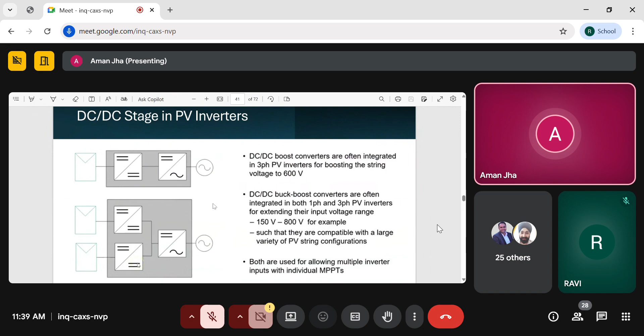So in the PV inverter case, the first stage is the DC-DC converter, mostly a boost converter. The boost converter is used to fix the input voltage coming from the panel, similar to the bus voltage in an AC-DC converter. Here it's also named bus voltage, fixed up to 600 volts depending on the panel voltage. This is one use case of the DC-DC stage in PV inverters.